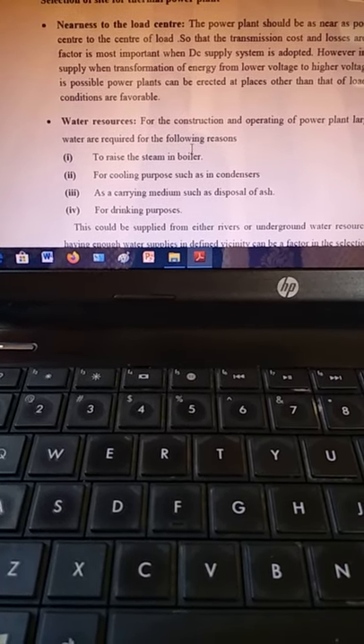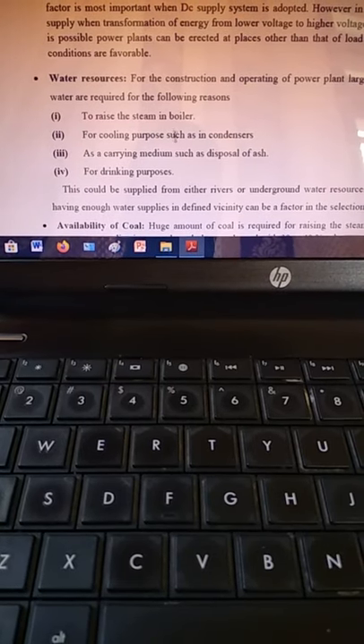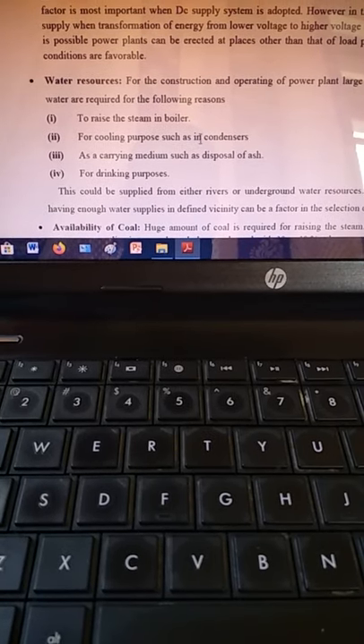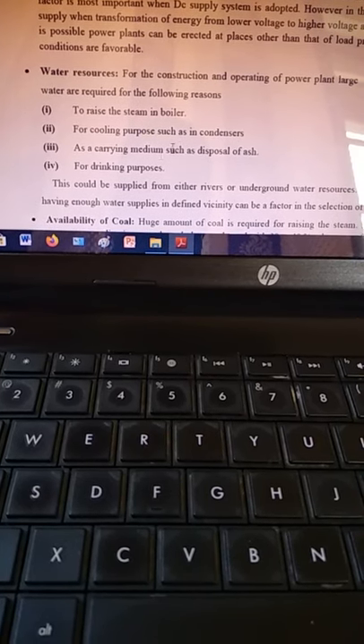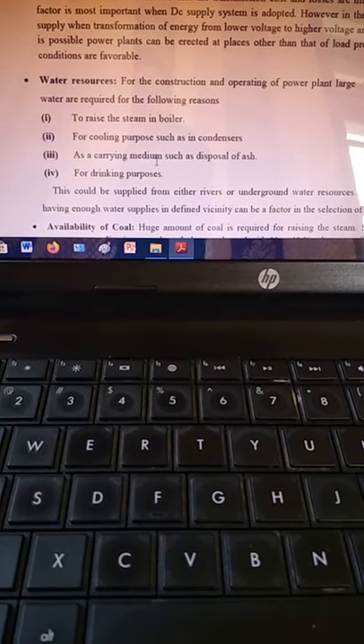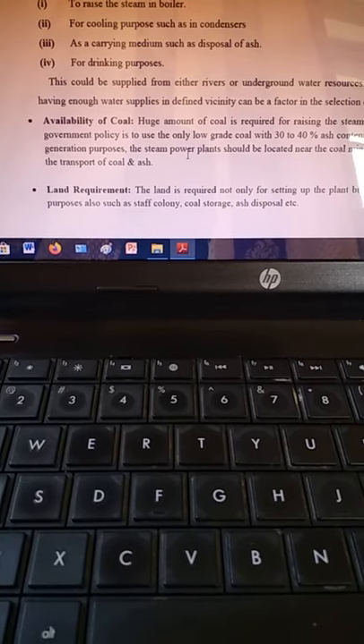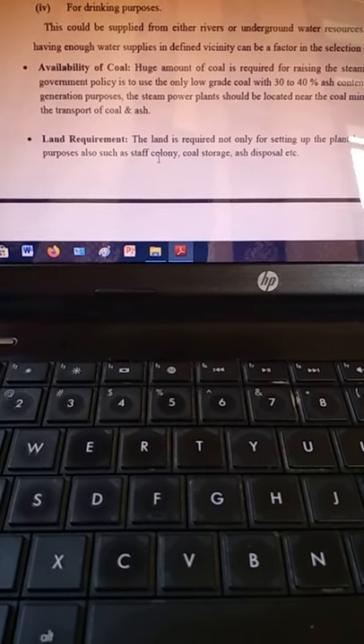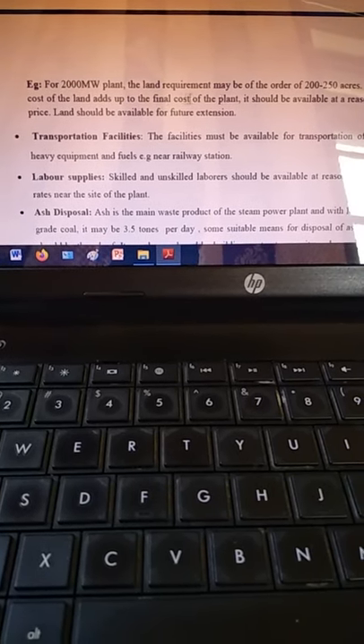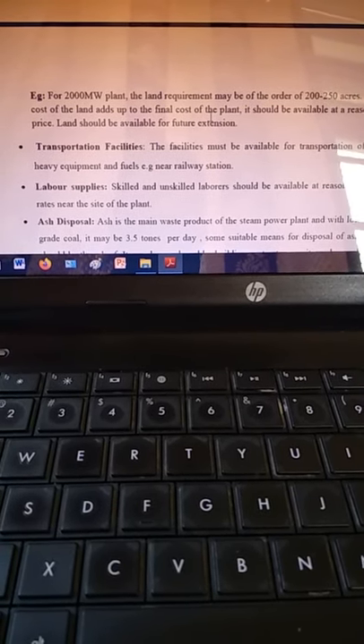Water has various functions: it is supplied to the boiler, used for circulation in cooling towers, and for cleaning the plant or boiler. The main function is as feed water for the boiler to produce steam. Availability of coal of suitable quality should also be near the power plant. For land requirement, a 2,000 megawatt plant requires approximately 200 to 250 acres of land.